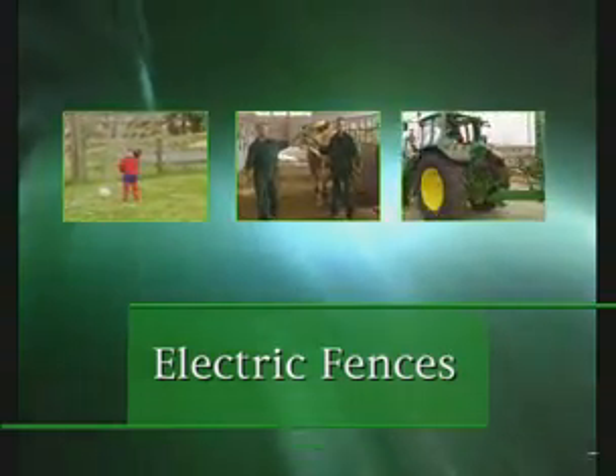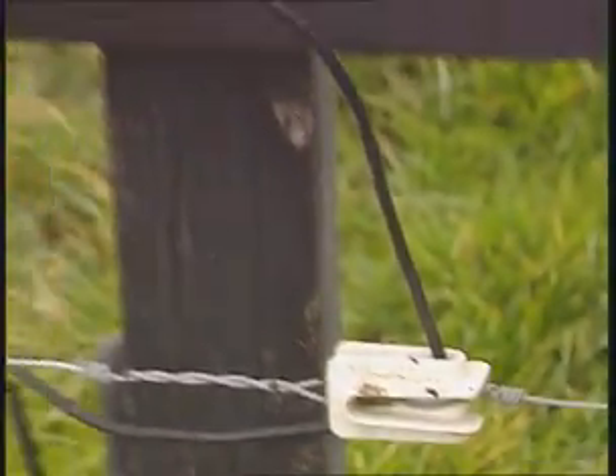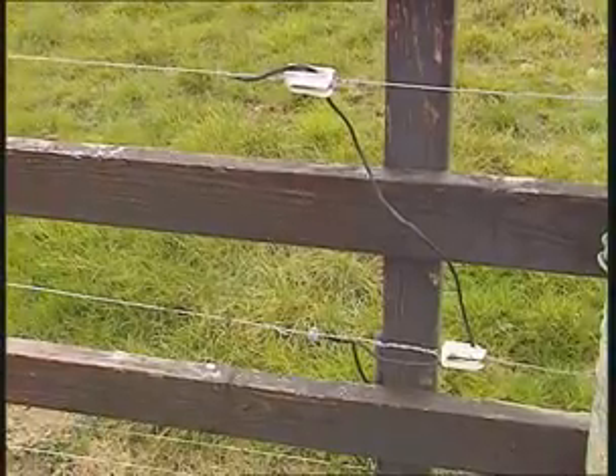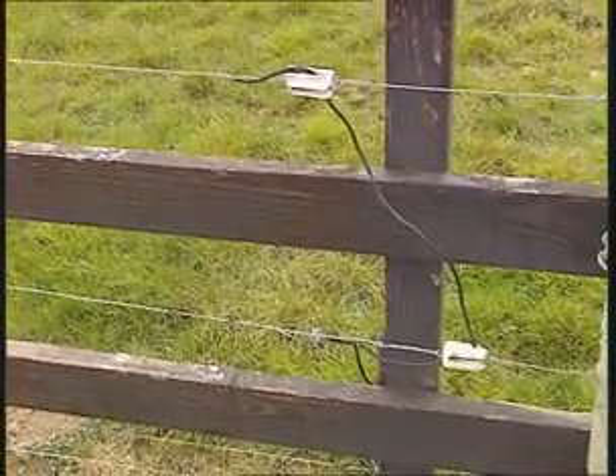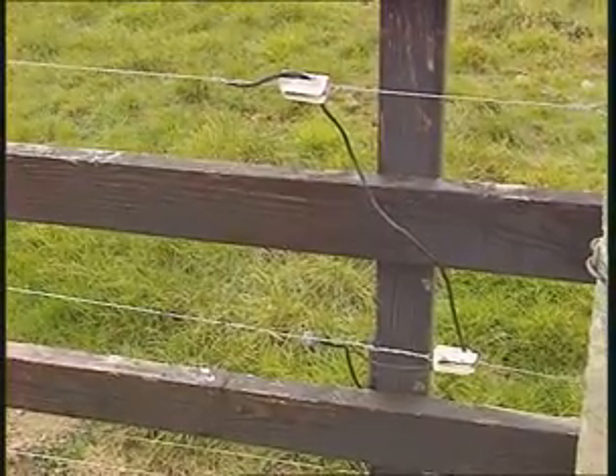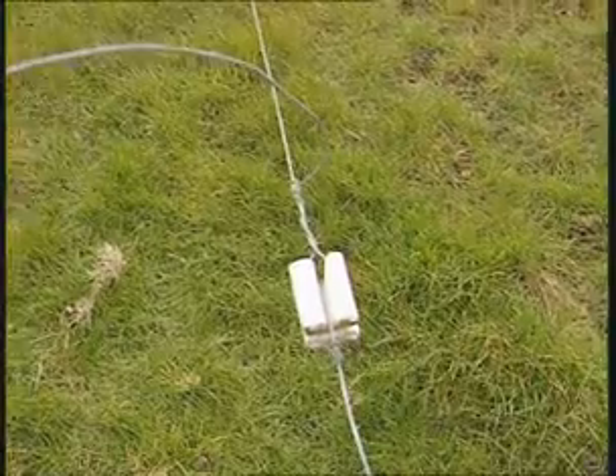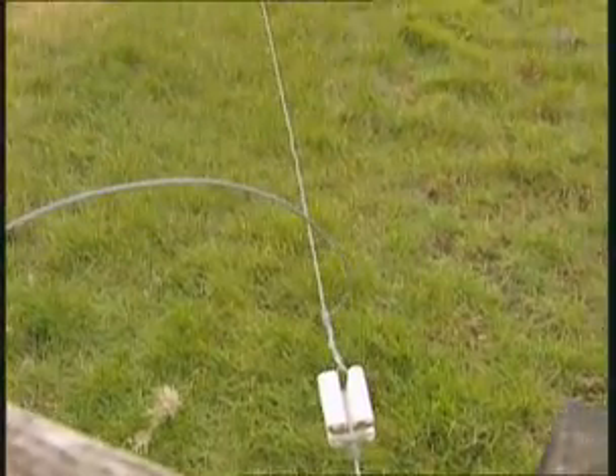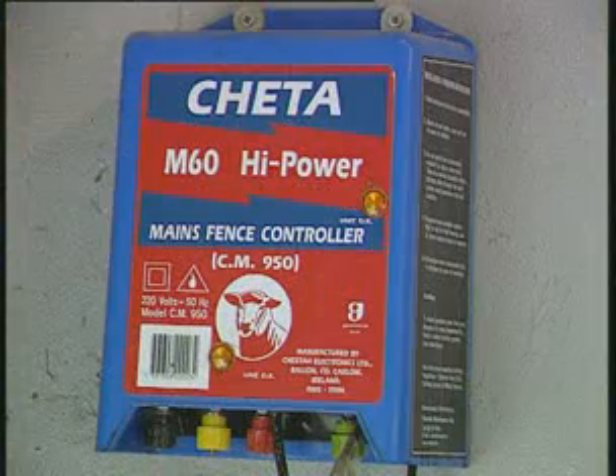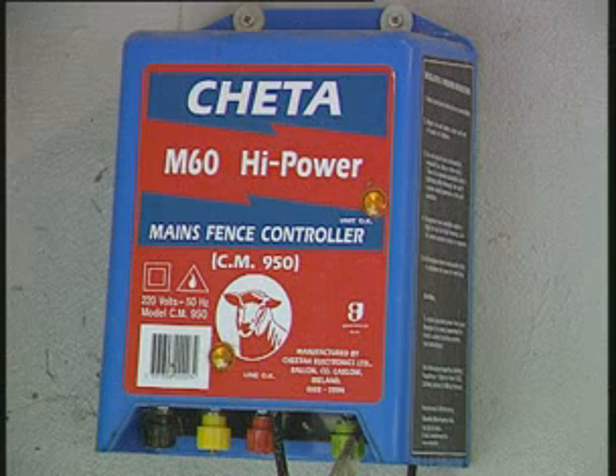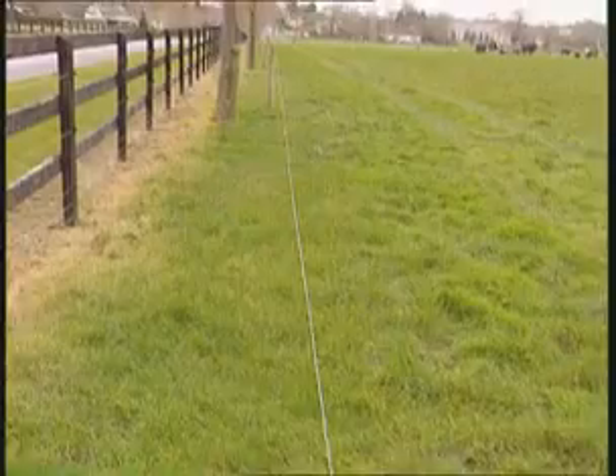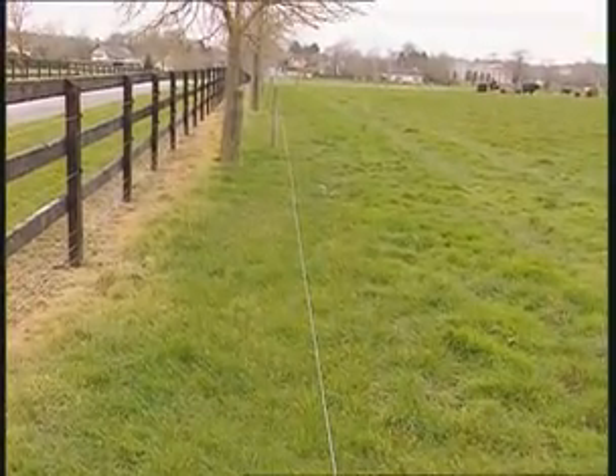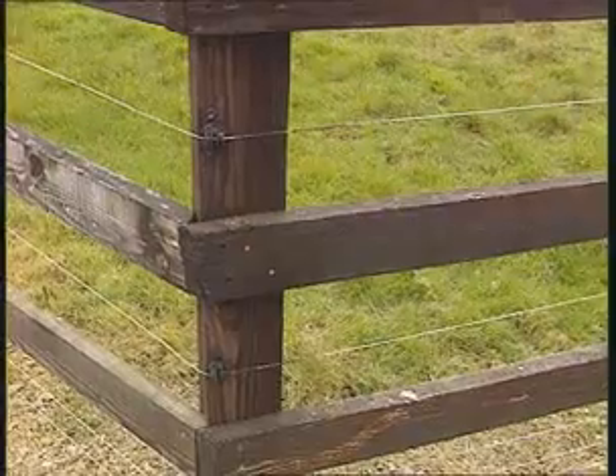Electric fences. Mains electric fence equipment is widely used on farms and has featured in a number of fatal electrical accidents. To prevent danger, the maximum discharge energy should be 5 joules per impulse. The control unit should not be installed near flammable materials. Should be protected from mechanical damage.